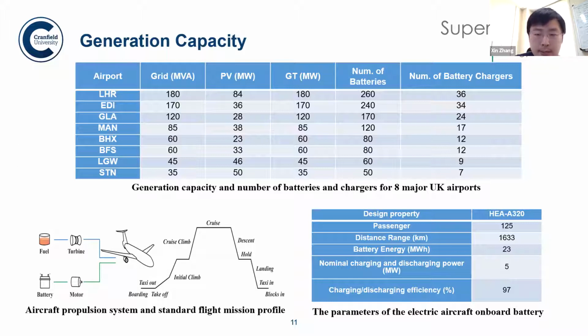The size of the grid connection is assumed to be the same as the gas turbine size within the airport. Why make this assumption? Because it's considered an N-1 reliability criterion: if a gas turbine goes down or has an outage, we still have the same amount of power available from the grid.